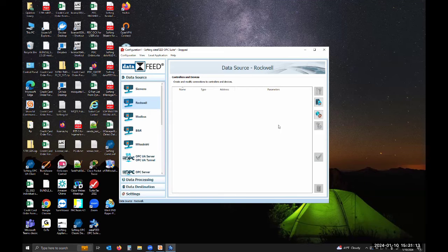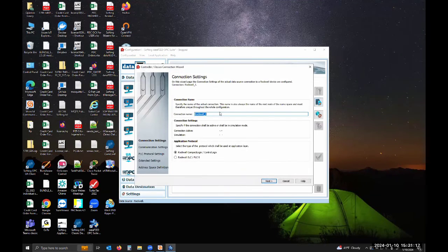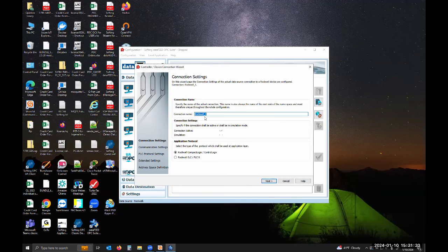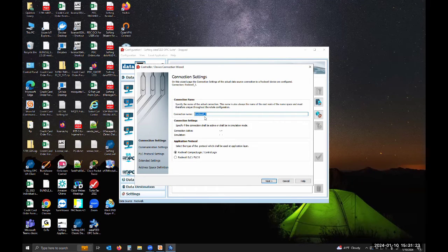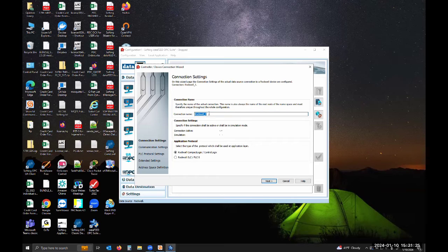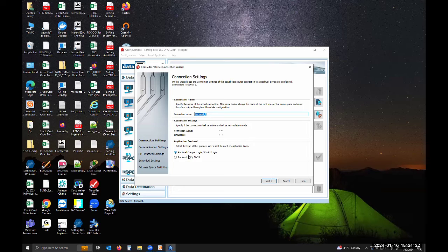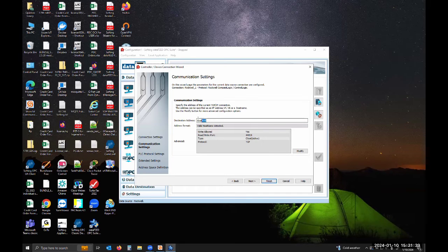To add a Rockwell PLC, you click on add new data source. It'll allow you to name that data source whatever you want. This is how it's going to show up in the OPC UA configuration. You need to also select which controller you're connecting to, if it's Compact Logix, Control Logix, or the older SLCs or PLC 5s. Once you've done that, you can hit next on the destination IP address.